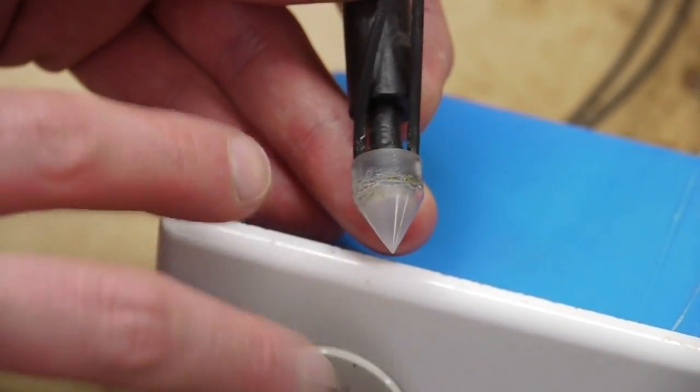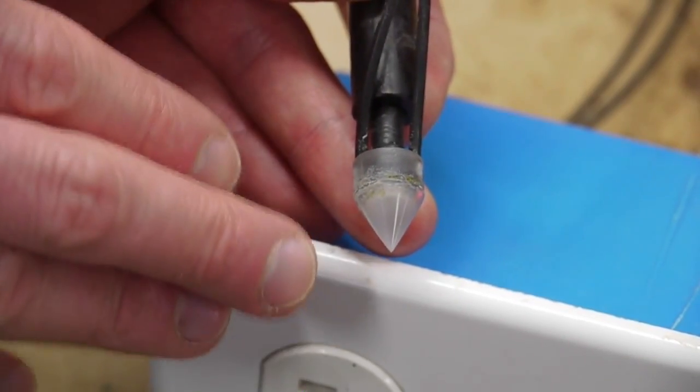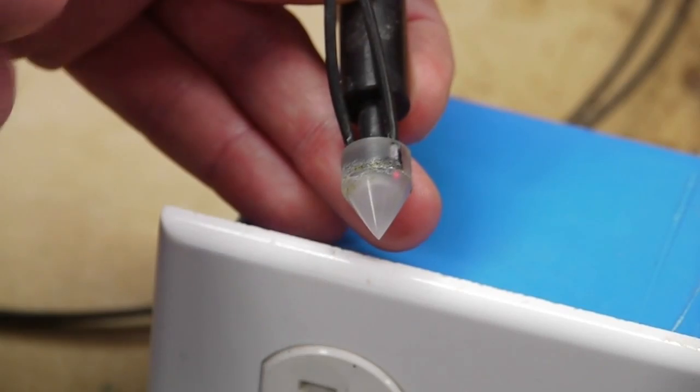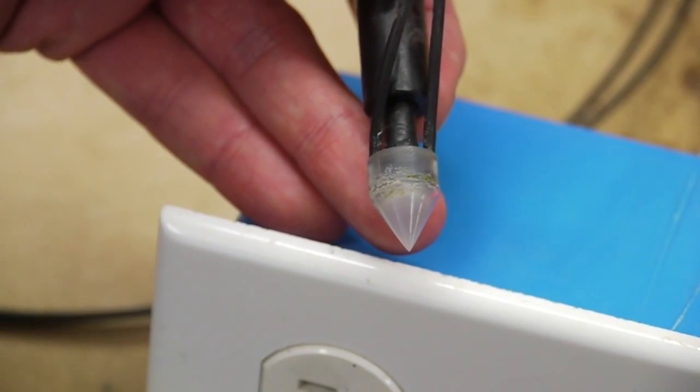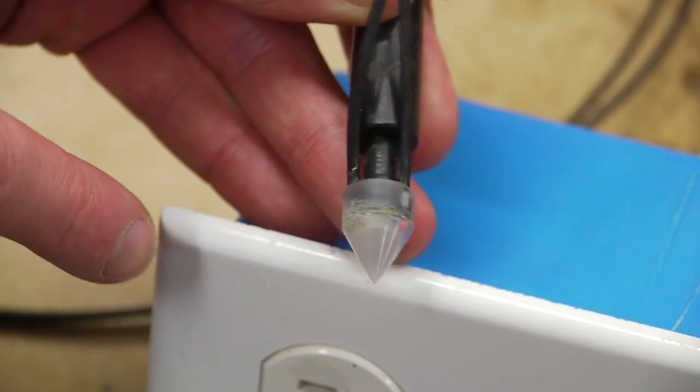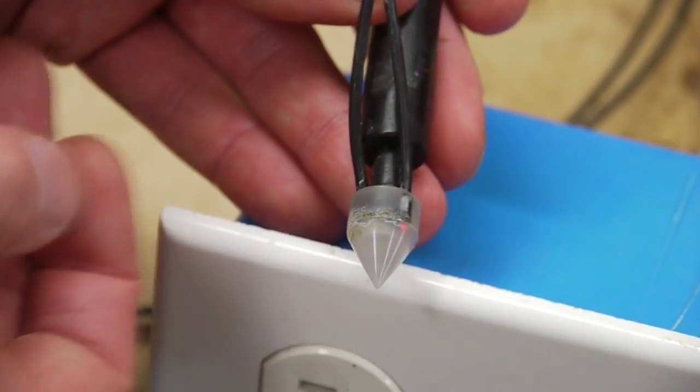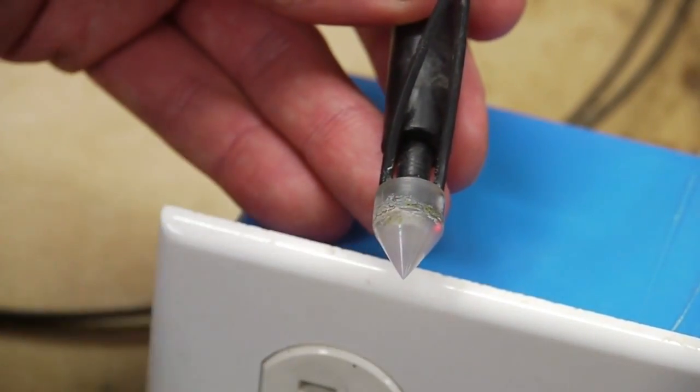So it's a very robust sensor. It's actually hard to fool this because it's sort of sensing in this entire area of the cone here. So the level that the water has to come up to to make the light diminish to the threshold value is very repeatable. And there's no moving parts in here and this thing is essentially sealed. So it's a very high quality robust sensor.